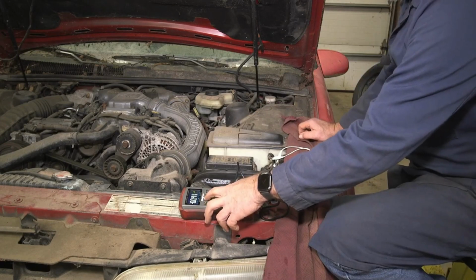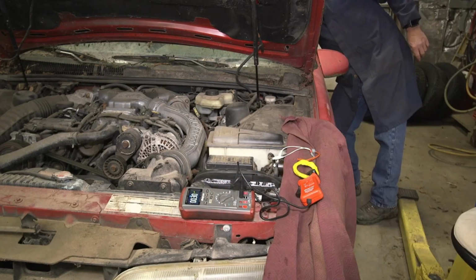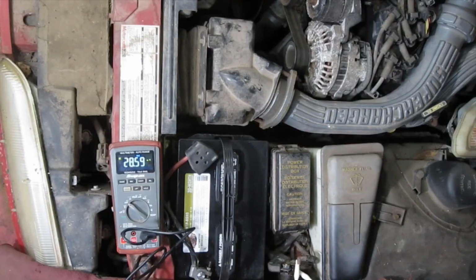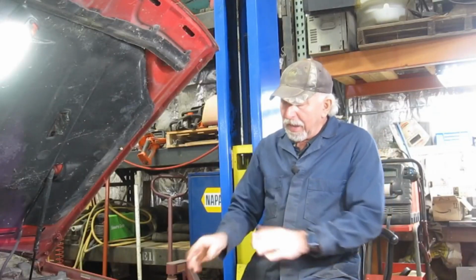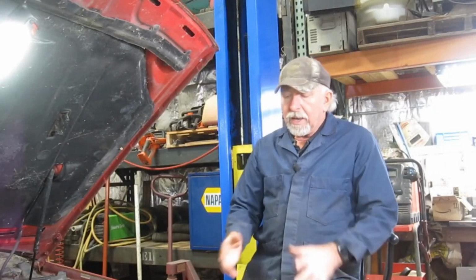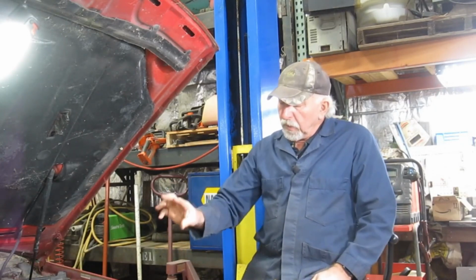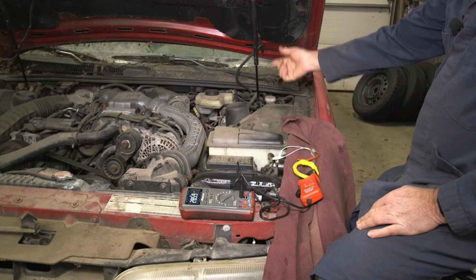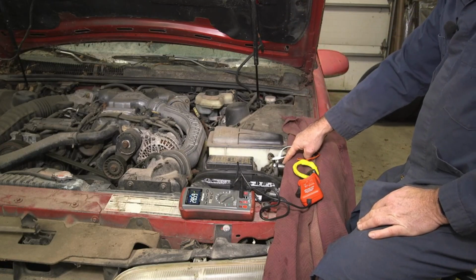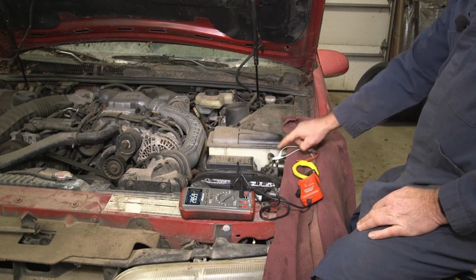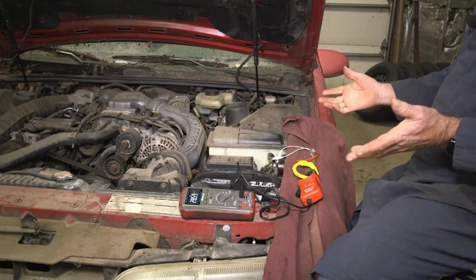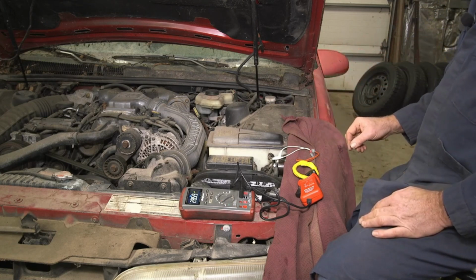Let's go ahead and put it on record. Okay, we have a highly accurate number here — we've got 2.8, we'll call it 2.86 amps coming into the solenoid. That's well within the acceptable range, a little on the light side. So we know the solenoid has enough current coming in, and we know it audibly clicks, so obviously we've got a mechanical problem in the solenoid itself.